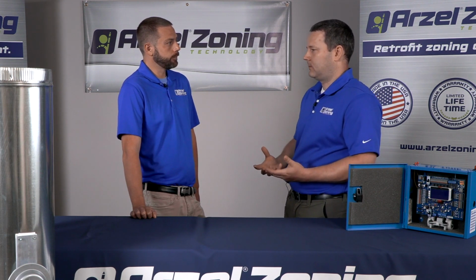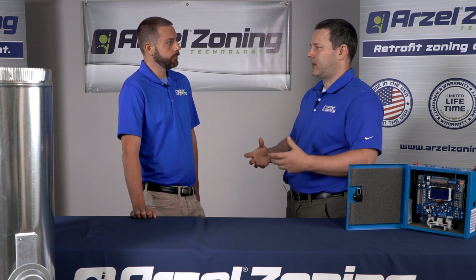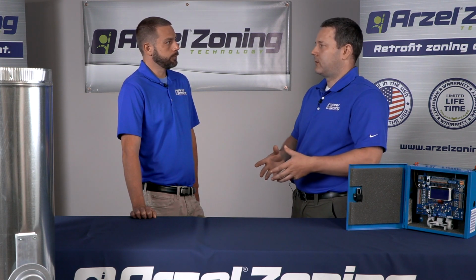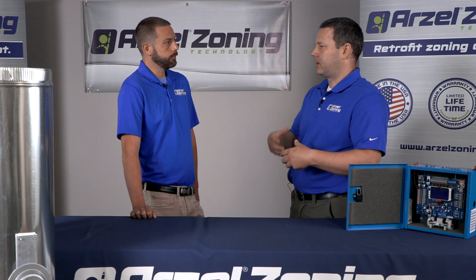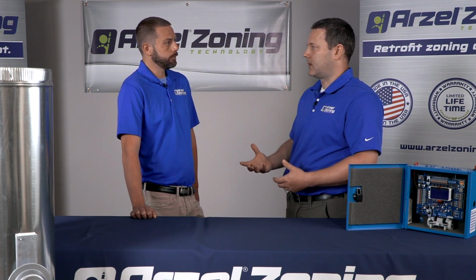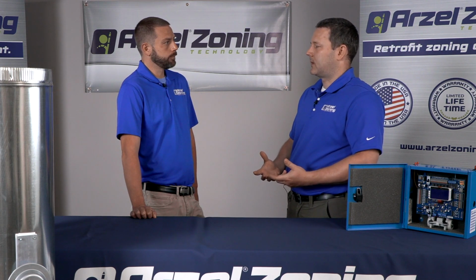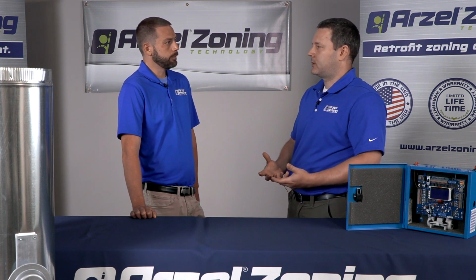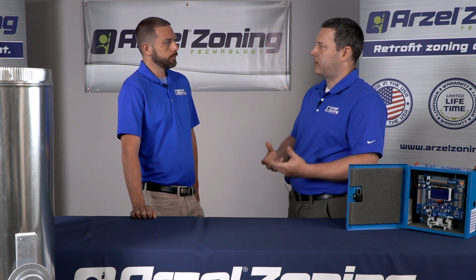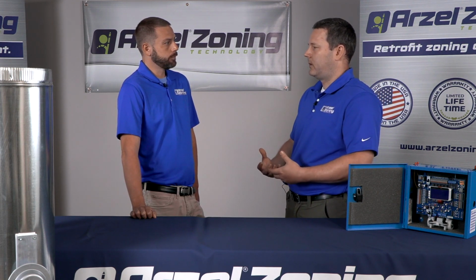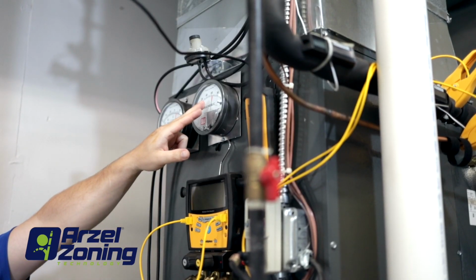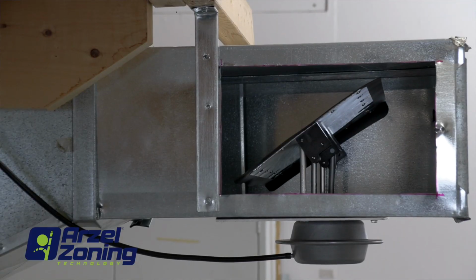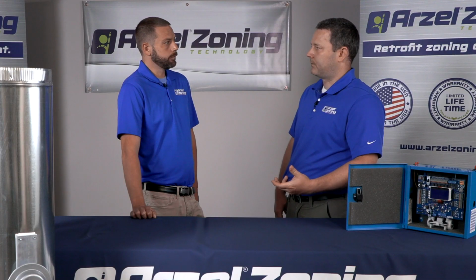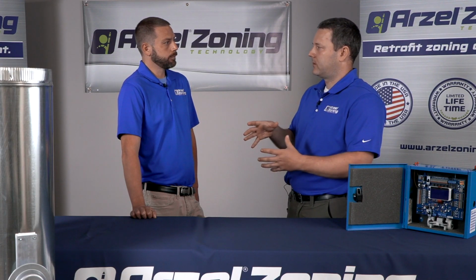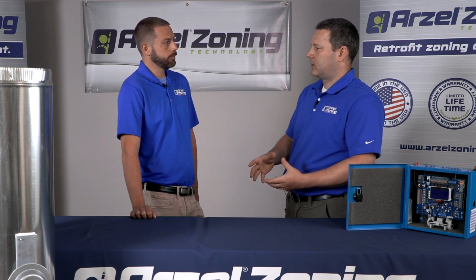The reduction of life on the equipment comes right down to actual design. If my furnace is already too small or too large for my ductwork, so I'm running high static before I even put zoning in, then I'm going to run into a problem with life expectancy on that equipment. Normal design application without zoning is your ductwork should be between 0.4 and 0.5 total external static pressure. Once we apply zoning, we want to push that up closer to the maximum that the blower performance data chart allows for in the furnace manual. So with our smallest zone calling by itself, we want to see that around 0.7. We're within the range we look for, and that's not going to have any impact on equipment life.